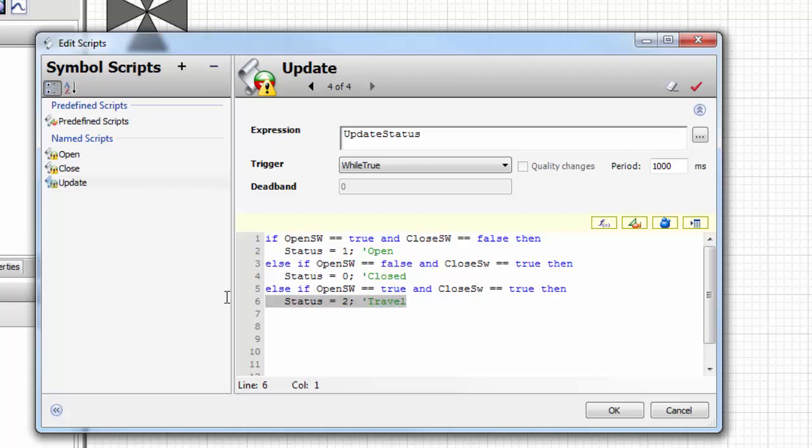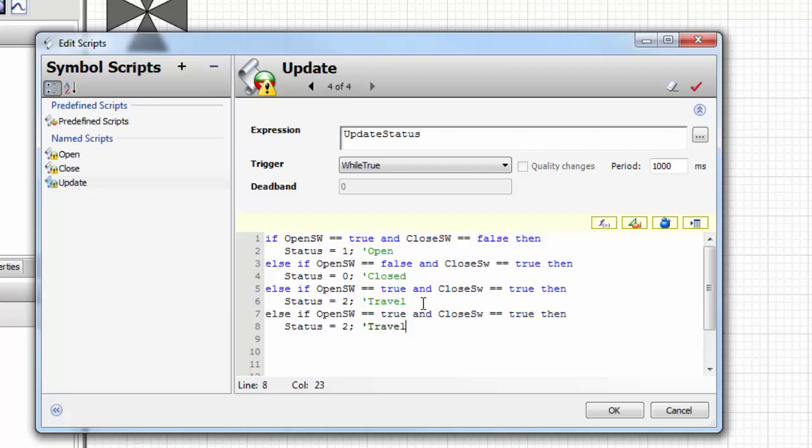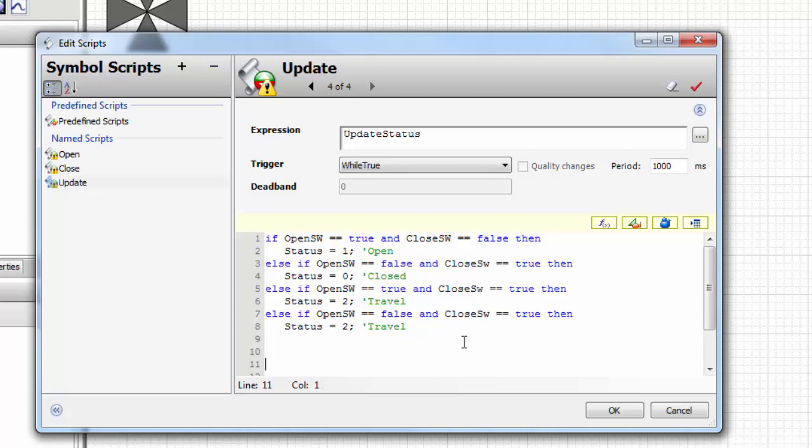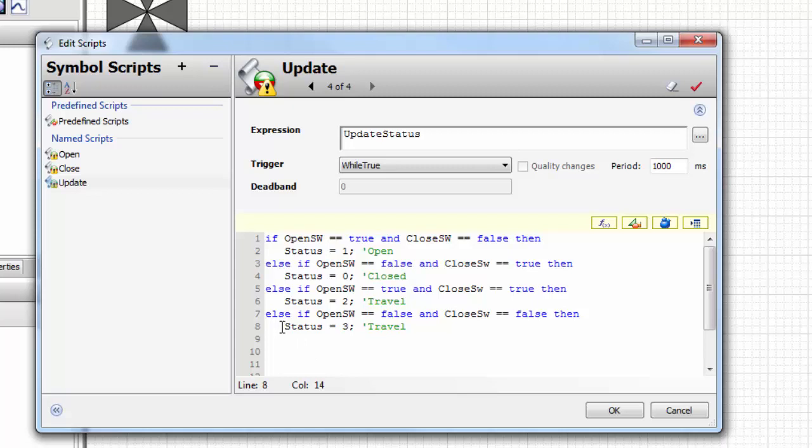The next condition: if the open switch is false and the close switch is false, then we're going to say the status is a three for trouble. That means the valve is stuck, the power is out, something has happened.